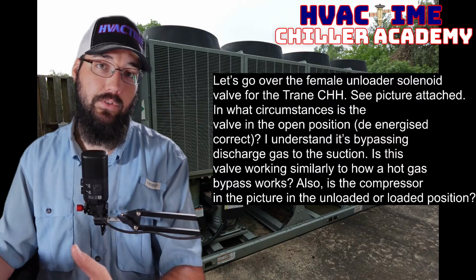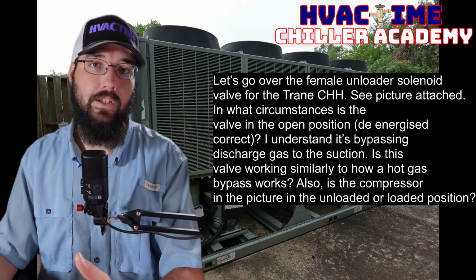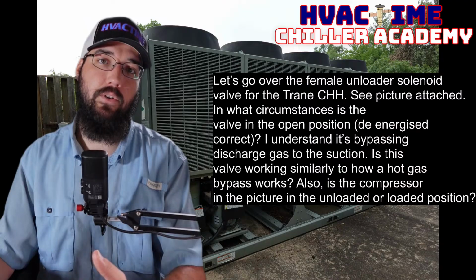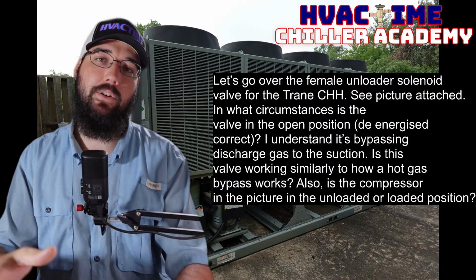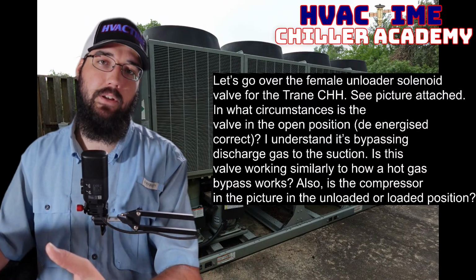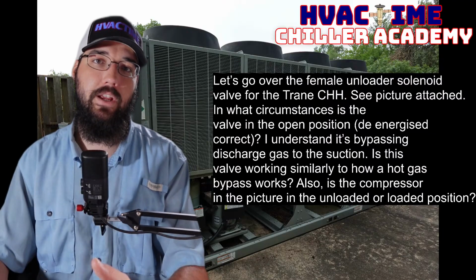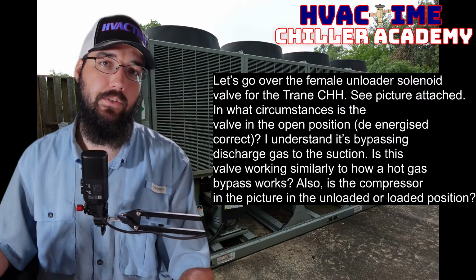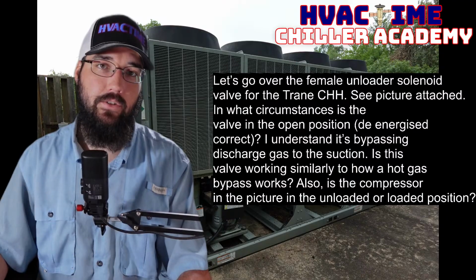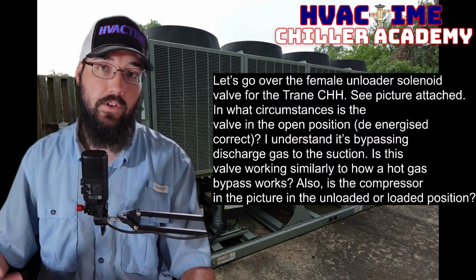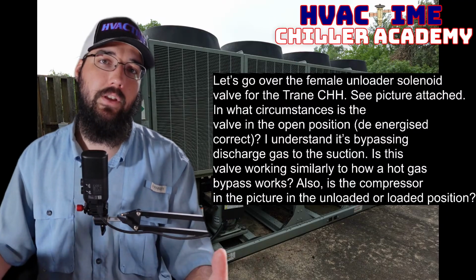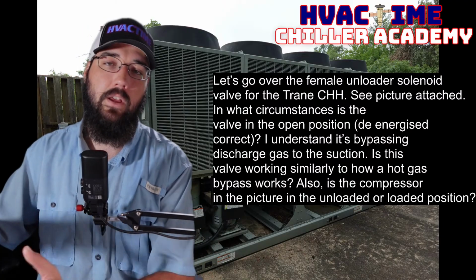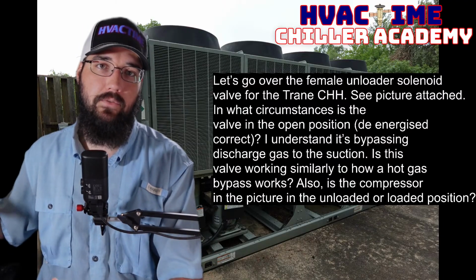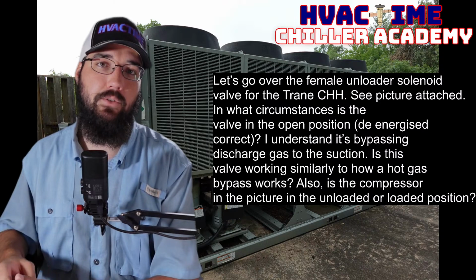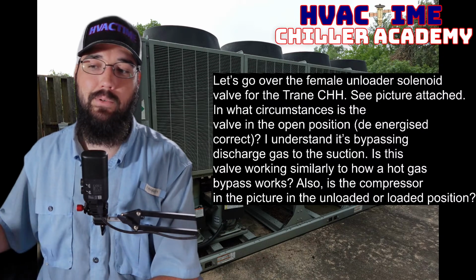Now, the slide will still technically function, so that part may still be functioning, but you're not going to be able to get to capacity because majority of your discharge gas is just getting routed right back into the suction, and it's just cycling internal to the compressor. There's no actual flow happening, which does cause higher temperatures in the compressor. Like there's a whole rabbit trail of possible symptoms if it was allowed to run like that over an extended period of time.